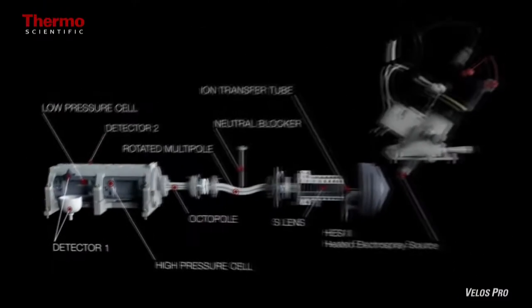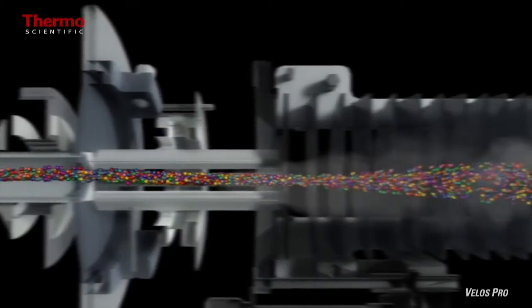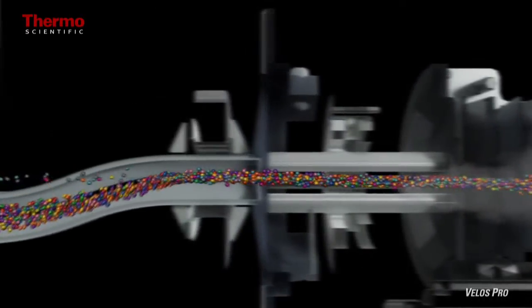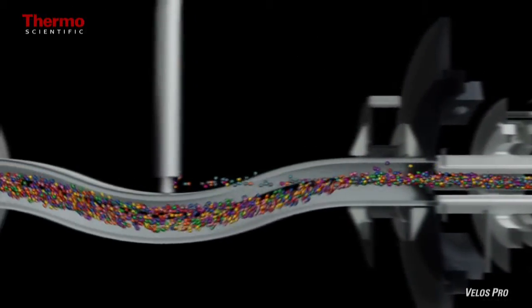One, we've improved the robustness dramatically by adding a novel beam blocking technology. For the first time ever, we're able to stop neutrals and contaminants outside the path of the ion optics. This technology allows us to run longer between cleanings and handle dirtier samples.